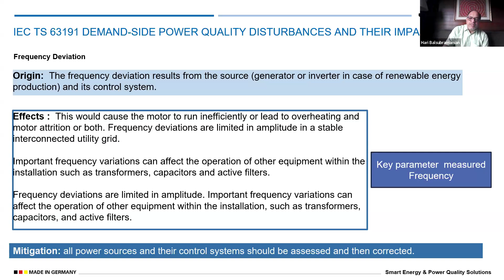So the frequency deviation results from the source. This has a lot of effects on the loads. I'm not going to read through most of this content, as I'm also running short of time. This is currently a very small issue in India, I suppose. This frequency deviation can happen when a big plant has its own source of power, especially when they have multiple sources like PV, cogeneration plants, and also a windmill, along with certain kinds of loads from the utility side. But ultimately, this needs to be taken care of. The key parameter to be monitored is frequency. So all power sources and their control power systems should be assessed for mitigation of this frequency deviation.